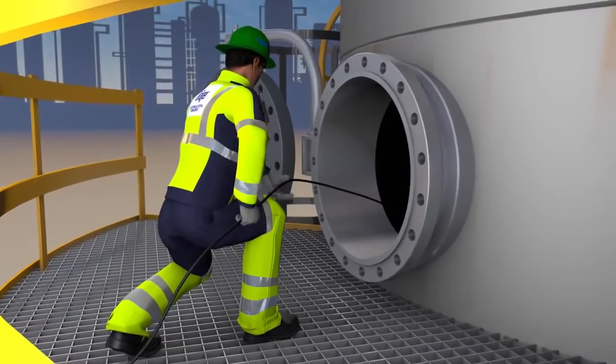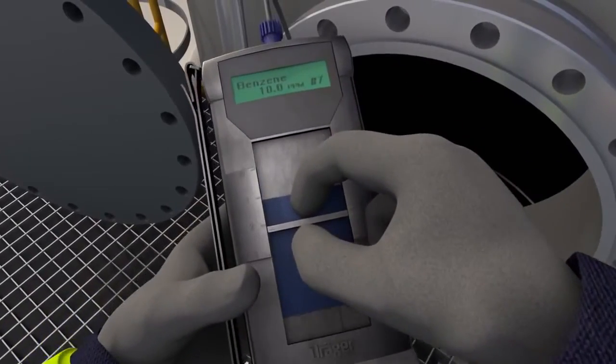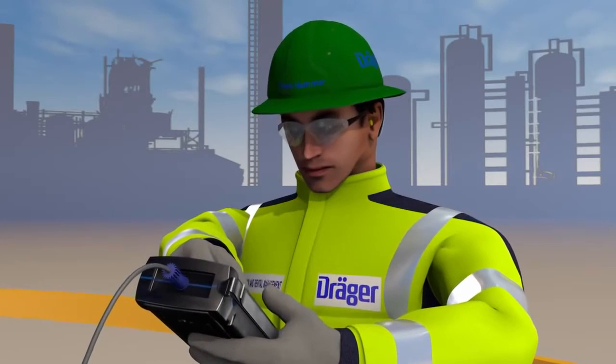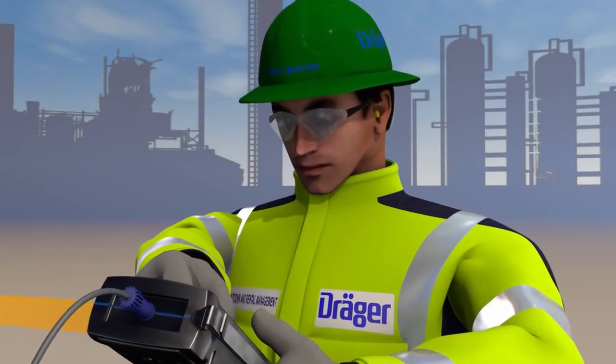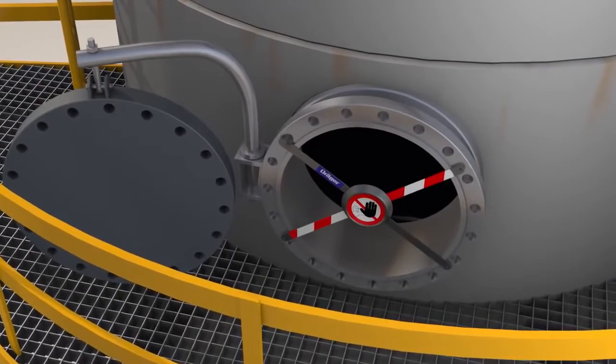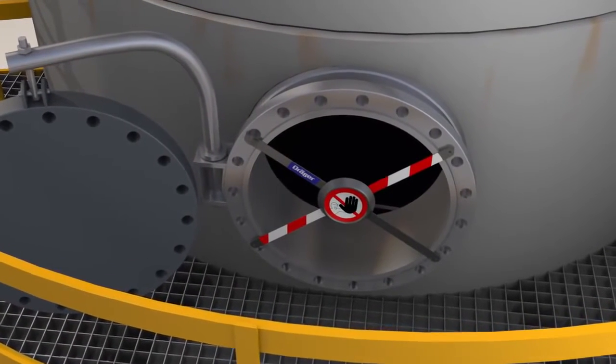Based on the individual circumstances on site, another measurement is performed according to the measurement strategy. This time, the gas analyst uses the Dräger Chip Measurement System (CMS). With this instrument, he can conduct substance-specific measurements, and it is precisely during this measurement that the device flags up a relevant reading. At 10 ppm, the benzene content where this crew is working is too high. The Dräger gas analyst cordons off the area and initiates additional steps.